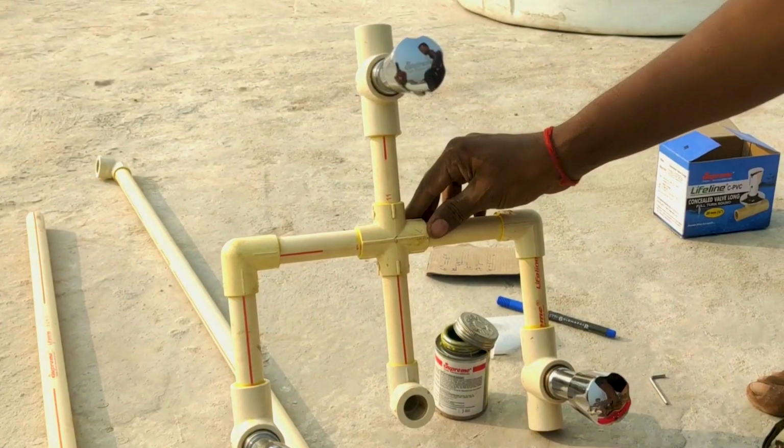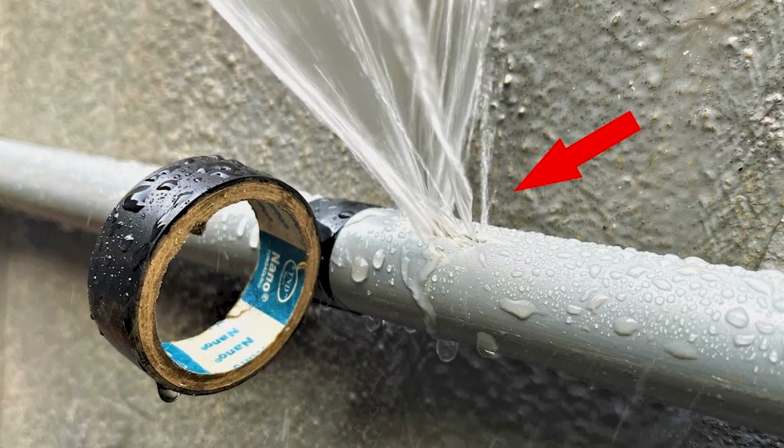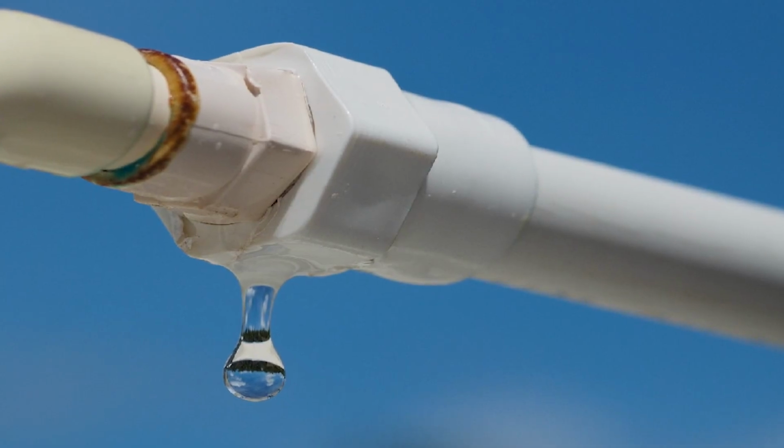I don't recommend it. A lot of times you'll see that outside of city limits where codes aren't heavily involved and they're not getting inspected by city inspectors and so forth. It's just not durable. It doesn't handle ground shifting well. Texas soils move a lot because we have really dry, hot summers, and the ground will start to separate. We've all seen the big cracks in the ground. As that ground separates and pulls apart, PVC just doesn't handle it well. The fittings will break. The pipe can separate from the fittings, causing leaks, inconveniences, and so forth.